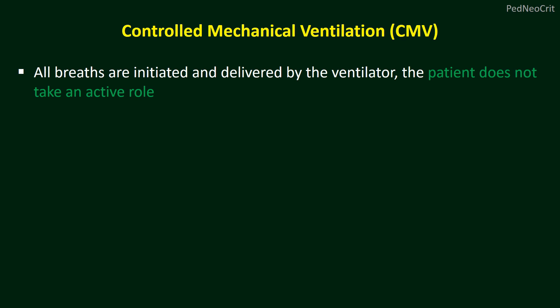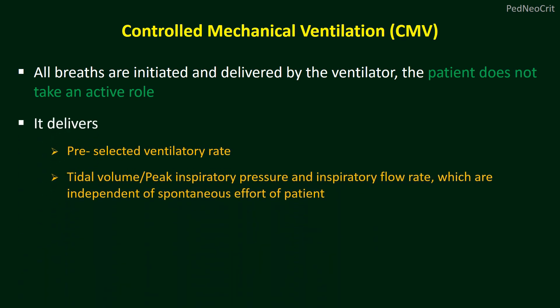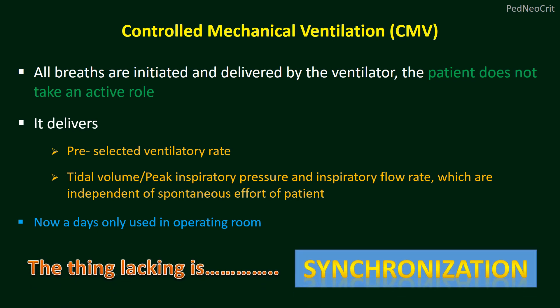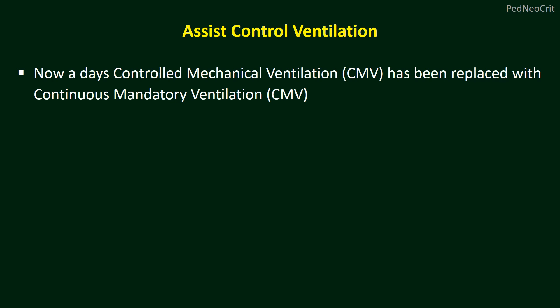In controlled mechanical ventilation or CMV, all breaths are initiated and delivered by the ventilator and the patient does not take an active role. It delivers a preselected ventilatory rate and tidal volume, or peak inspiratory pressure and inspiratory flow rate, independent of spontaneous patient effort. This mode is not routinely used in clinical practice — only in the operating room or for comatose or deeply sedated patients for a short period of time. What is lacking here is synchronization. Nowadays, controlled mechanical ventilation CMV has been replaced with continuous mandatory ventilation CMV, so do not confuse yourself.